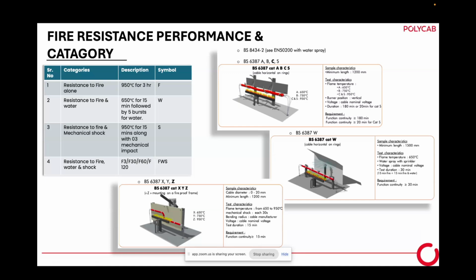Now coming to the left side: if a customer wants only fire resistance, and not water or mechanical shock resistance, he will take a cable which can withstand 950-degree temperature for 3 hours. As per IS, this is symbolized as F, but as per BS 6387 it is C.